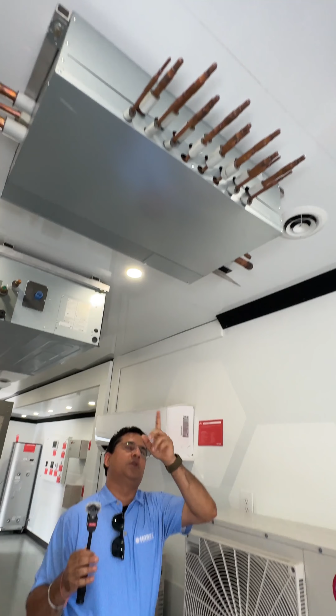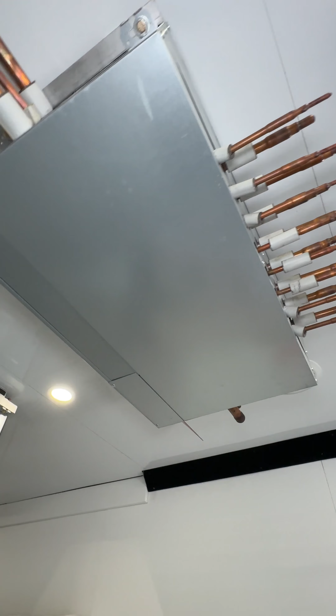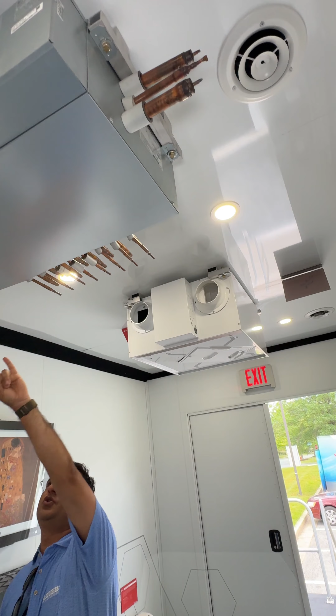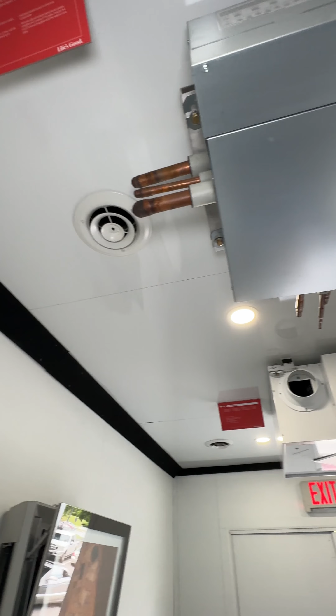Love it. So those are the indoor units. This is your heat recovery box for your VRF systems. 8-port box. Each port can have its own mode. You can have heating and cooling on that side. A unique feature for LG is the pipe-through. If you see both sides, you have the pipes coming in and out. That means you don't have to put in the Y branches. You can go up to 230K BTU. So you can go right through the box, you don't have to add the Y branch.